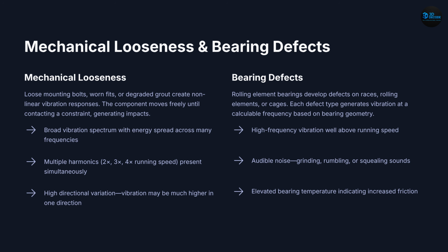Slide 9. Mechanical looseness. Loose components create wide-frequency vibration with multiple harmonics. Vibration varies with direction and load. This indicates structural or mounting issues.